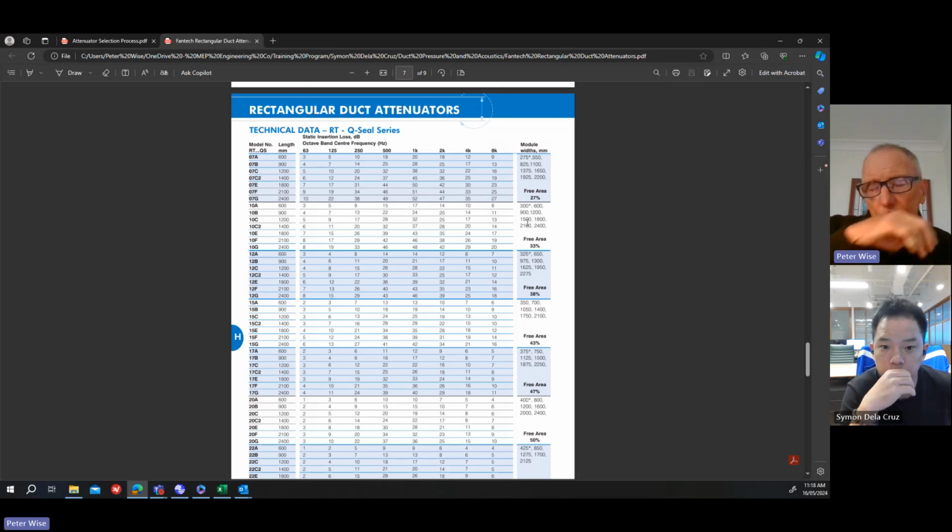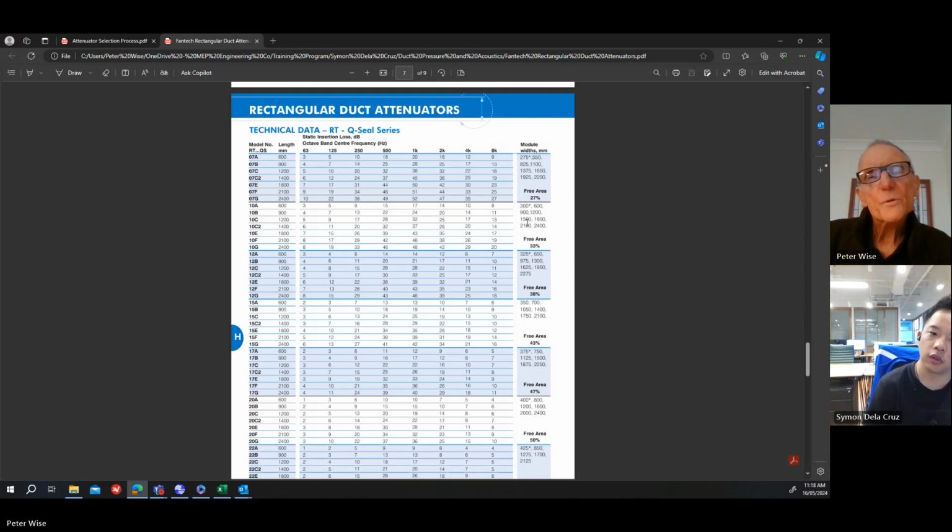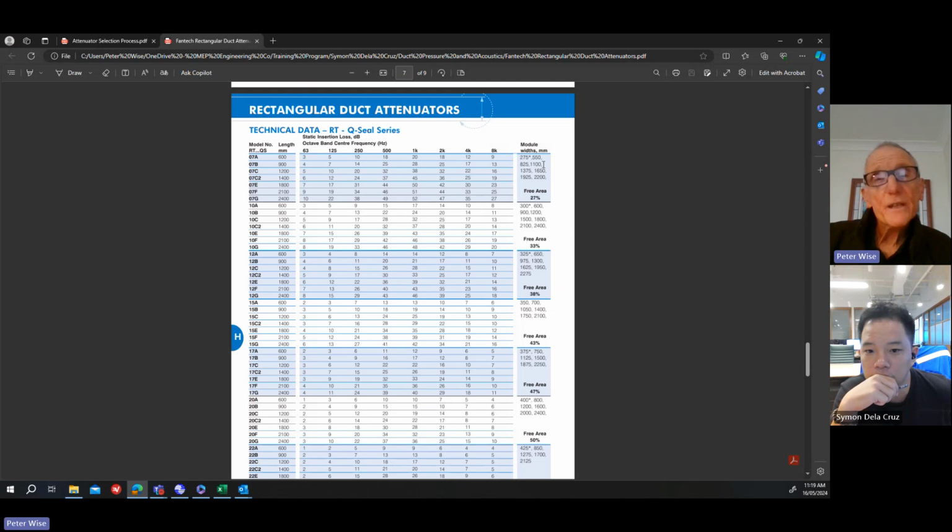So if you've got a duct, it's basically going to try and match up with the height, which could be important if it's in a ceiling. The height will be important, but if it's in a plant room, the height and the width can vary depending on how much space you've got. So from whichever one you choose, let's say you choose the 07C2, you've got these module widths. And if your duct is around, say, 1 metre wide, you might select 1100 for a width. And then from that, you know the area, you can calculate the height.